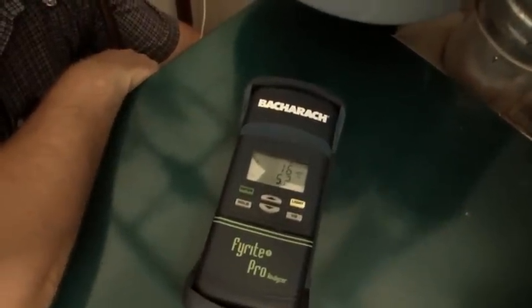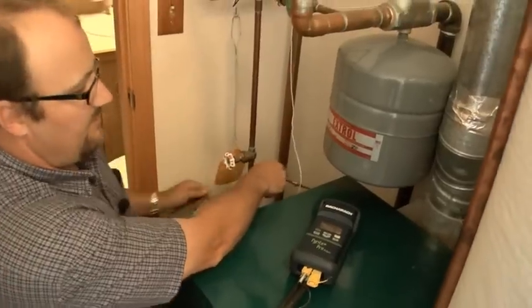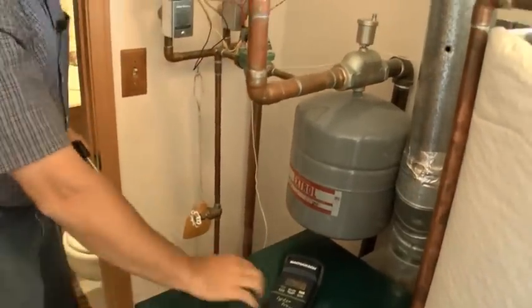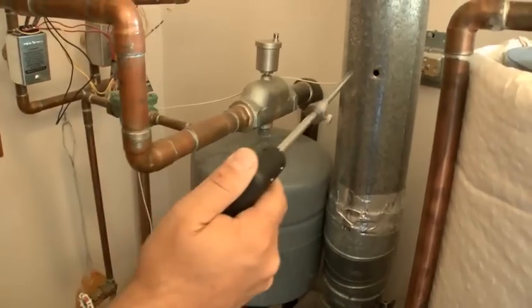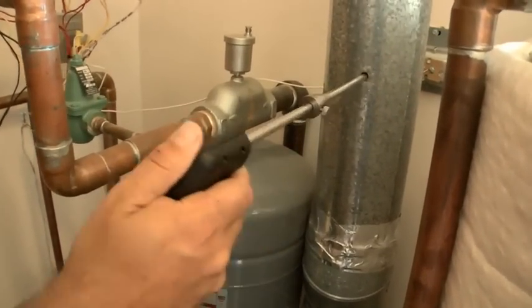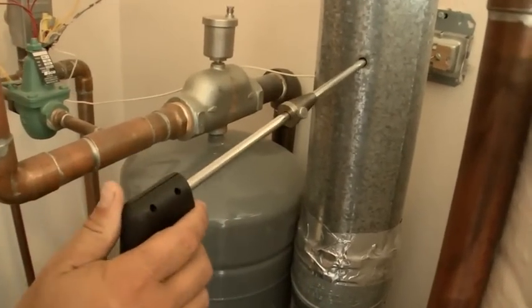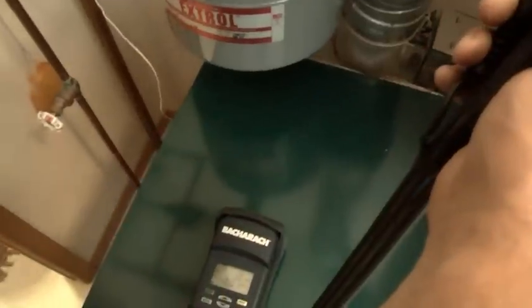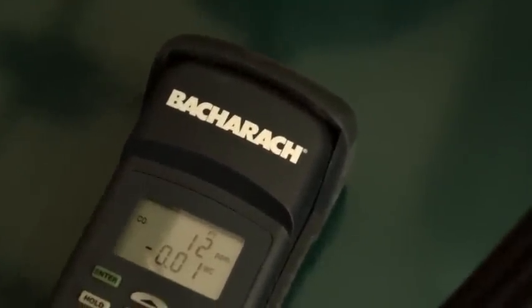Let's take a look at our CO one more time. We're at 15 parts per million CO, so that's pretty good. So we have a good burn. Take a look at our draft again, just to see where we are on draft. We're looking at inches of water column, a little different number than pascals. We have minus 0.01 inches of water column of draft. So we do have some draft.